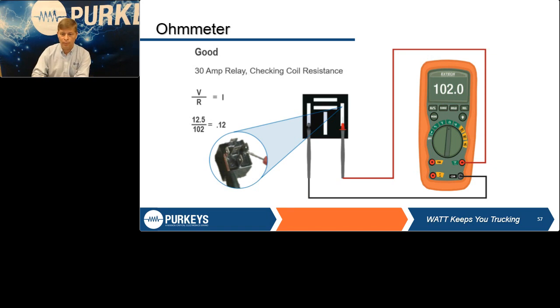why all this is important is if you take your voltage and divide it by the resistance, so we're going to use 12.5 volts, we're going to divide it by the 102 ohms, says that relay should pull 0.12 amps to activate. Not a whole lot of current.